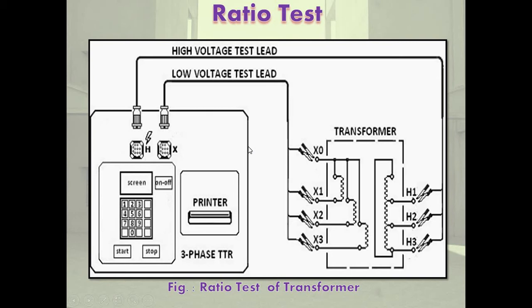This consists of a small portable transformer with a fixed primary and secondary winding, having a large number of taps connected to two selector switches. One is coarse and the other is fine, so that any desired voltage could be obtained for direct reading. The HV side of the transformer under test is connected to a low voltage main supply, say 400 or 220 volt, and the induced voltage on the secondary winding is compared with the voltage output of the ratiometer.